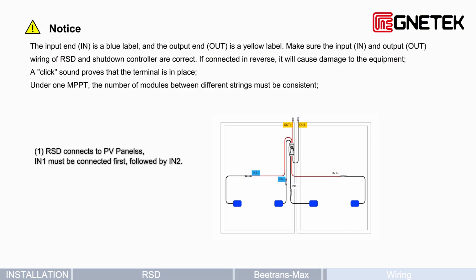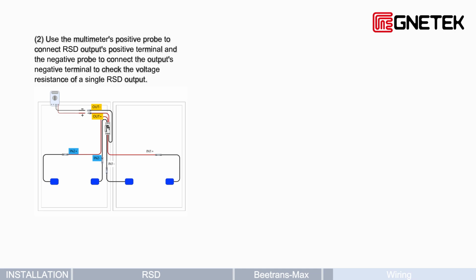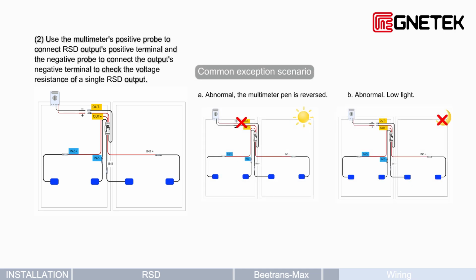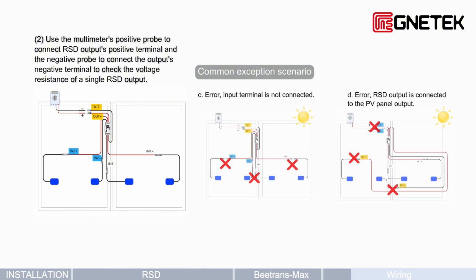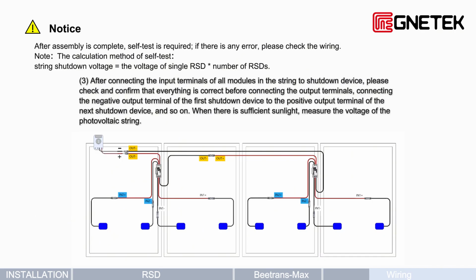RSD connects to PV panels. Use the multimeter's positive probe to connect the RSD output's positive terminal and the negative probe to connect the output's negative terminal to check the voltage resistance of a single RSD output. After connecting the input terminals of all modules in the string to the shutdown device, please check and confirm that everything is correct before connecting the output terminals, connecting the negative output terminal of the first shutdown device to the positive output terminal of the next shutdown device, and so on.